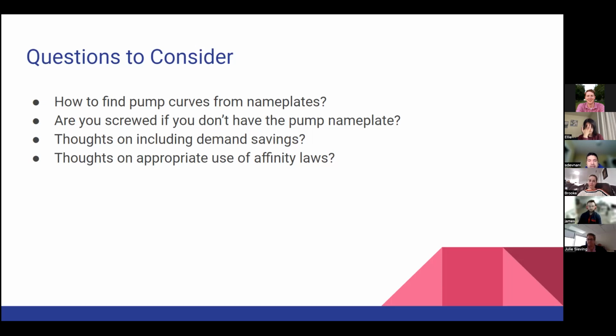Thoughts on including demand savings? Demand savings, I do not use them on VFDs. The reason is that all that has to happen in a given billing cycle is that the pump has to ramp up to 100% for 15 minutes, and then the demand savings are gone on the bills. That is what I like to do, under promise, over deliver. I take that as my little goodwill cherry on top, because they get the demand savings. Will they see it on the bills? Absolutely. But there is the off chance that on a VFD, you may not see the demand savings because of how it's run.